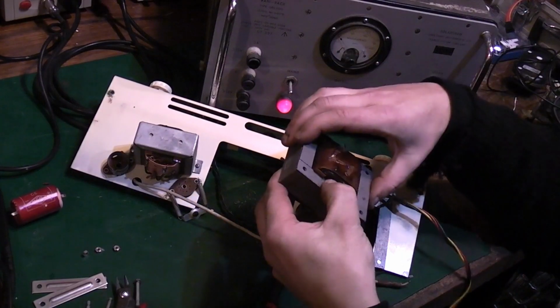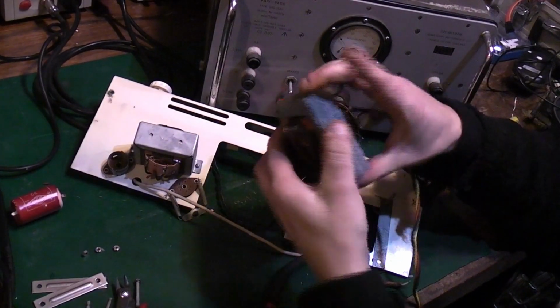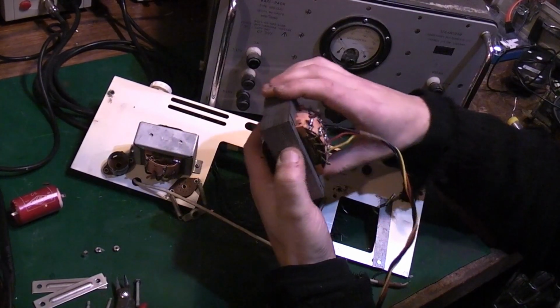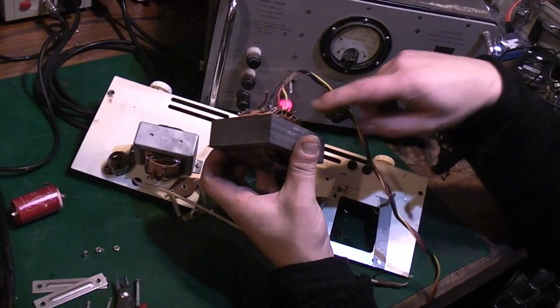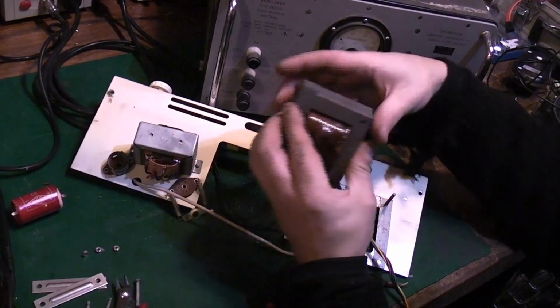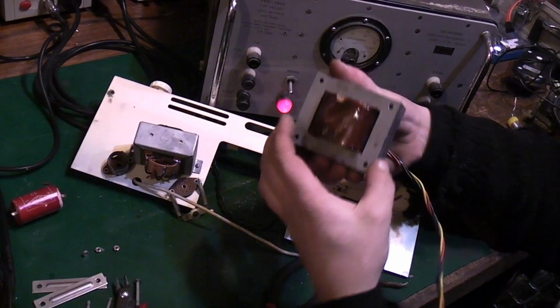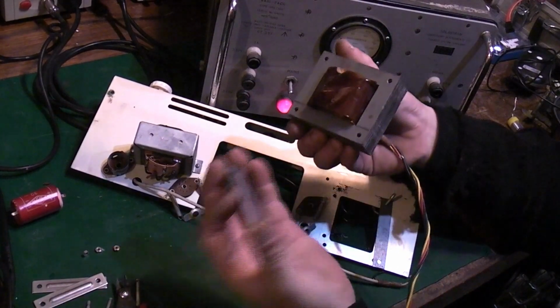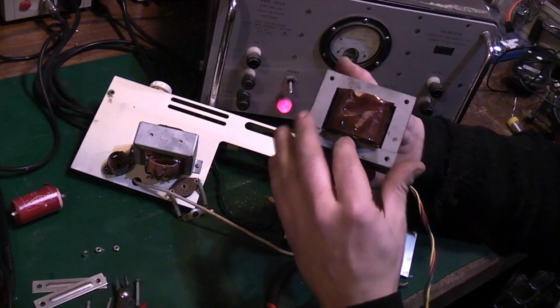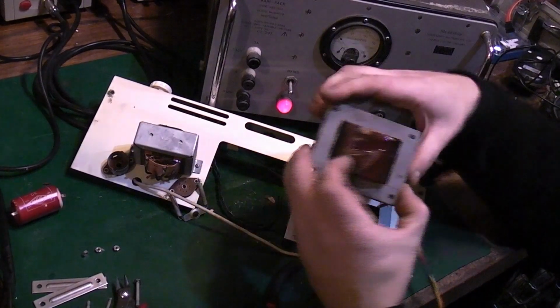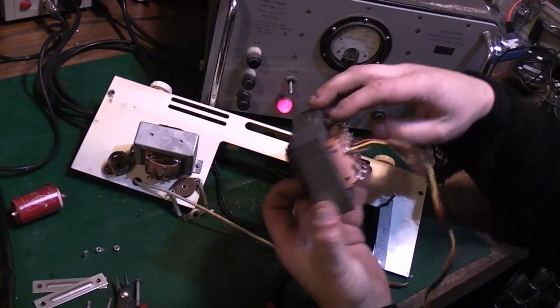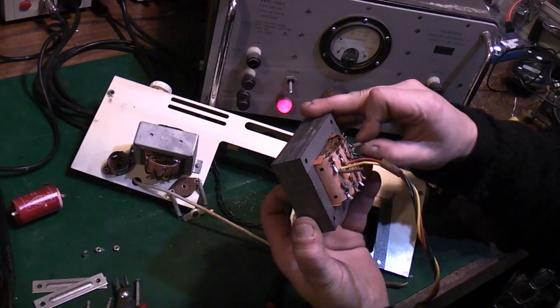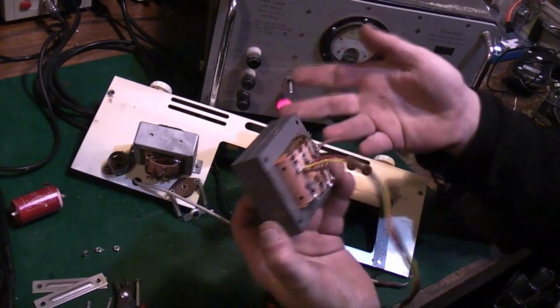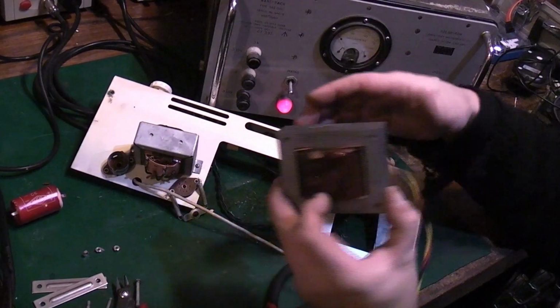It's like one of these transformers that's not actually held together - that might actually be repairable. There's a possibility, depending on how bad it's burnt out, because this is one where the whole laminations aren't fixed together. I can actually dismantle this transformer completely, pull the bobbin out, unwind it and see what's wrong with it. I mean, it's a lot of effort. It'll be thrown in a box marked bad, and if I need something in the future it might get looked at.